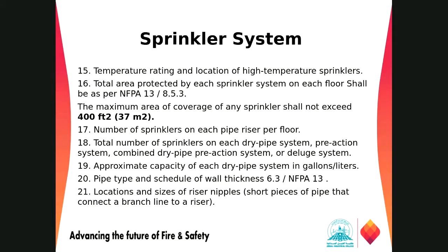Regarding the capacity of the dry pipe system in gallons, right? What is the capacity of the dry pipe system, if anyone remembers so far? The maximum capacity of the dry pipe system? That will be 750. Yeah, 750 exactly.